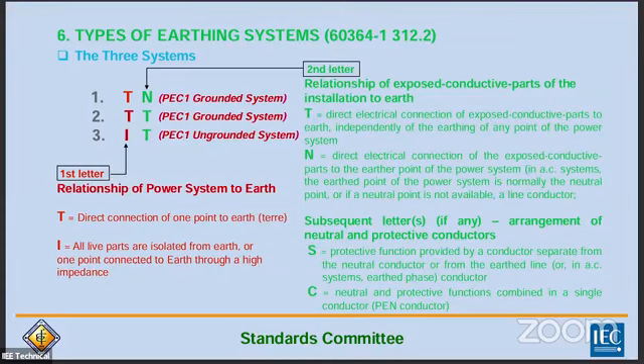Kapag T siya, direct connection of one point to the earth. Connect niya sa earth. Yung terre na word, which is the French word for earth. Then pag I naman, all live parts are isolated from earth or one point connected to earth through a high impedance, so meron naka-insert na high impedance dun sa common point na yon. So what is the second letter? So ito yung system earthing mo, T sa source.